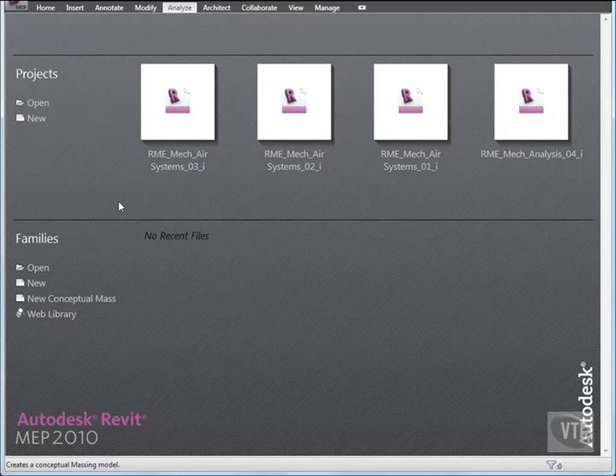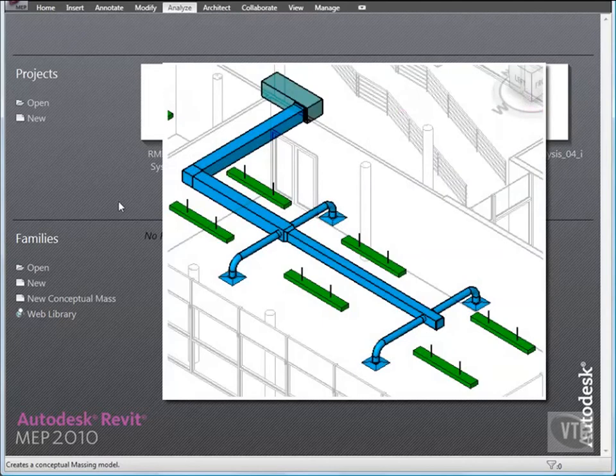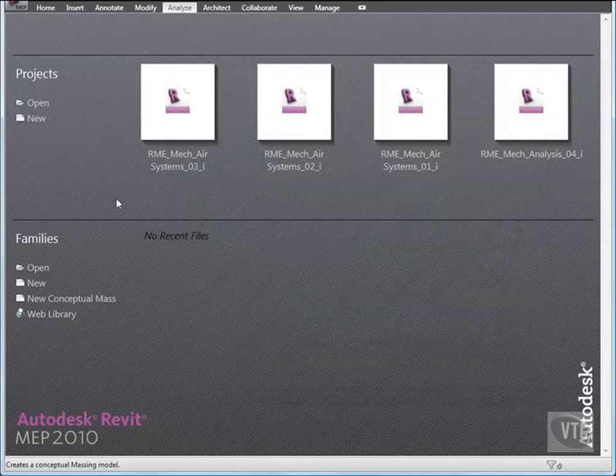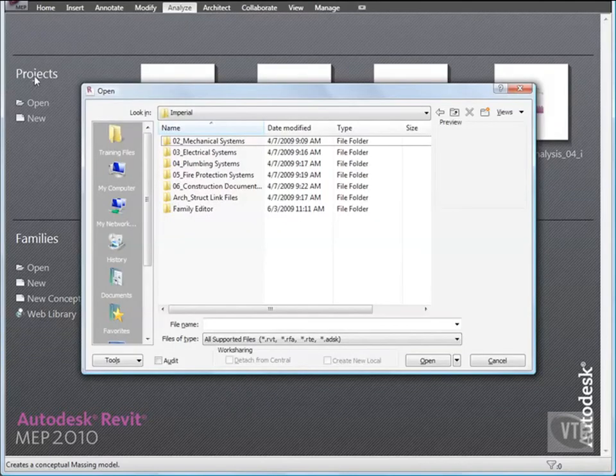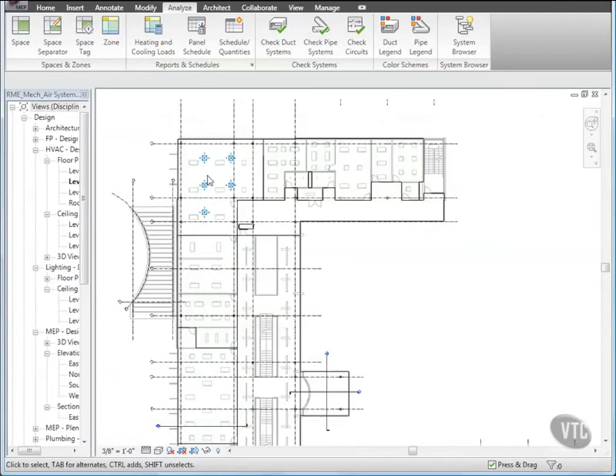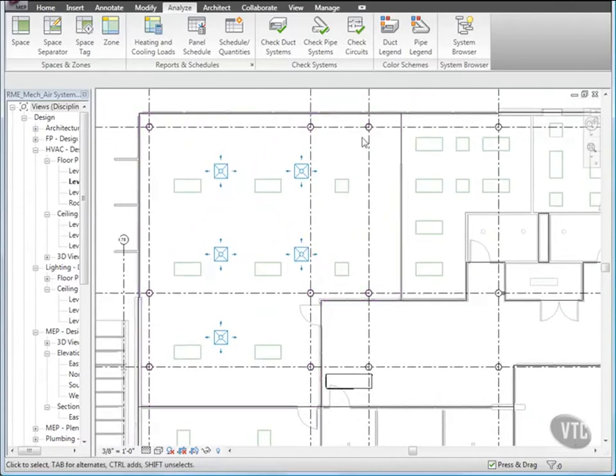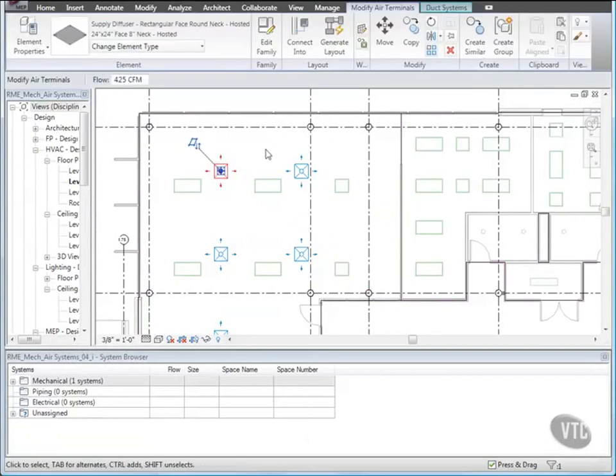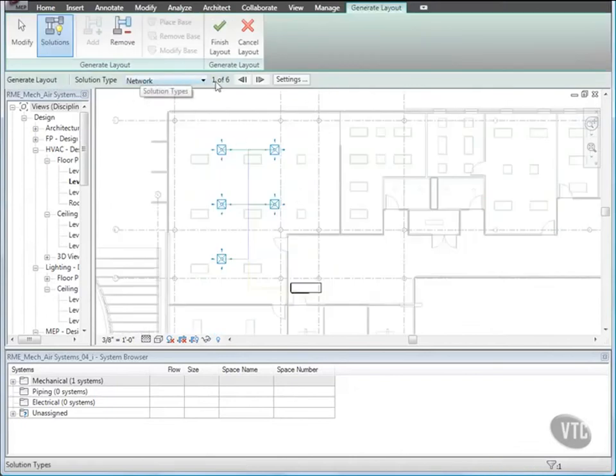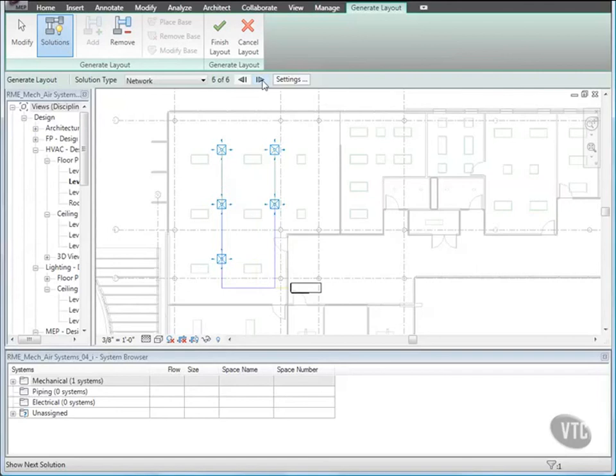In this lesson, you will create ductwork to physically connect system components. This workflow is Revit MEP recommended best practice for systems creation. Click the menu Browser and select Open, and from the Training Files Imperial Mechanical Systems folder, open the file RME-MEC-AIR-SYSTEMS-04. Zoom in to the space in the upper left corner. Display the system browser and select the upper left diffuser, and from the Layout panel, click Generate Layout. On the option bar, you can click the Next Solution and Previous Solution buttons to scroll through available solutions.